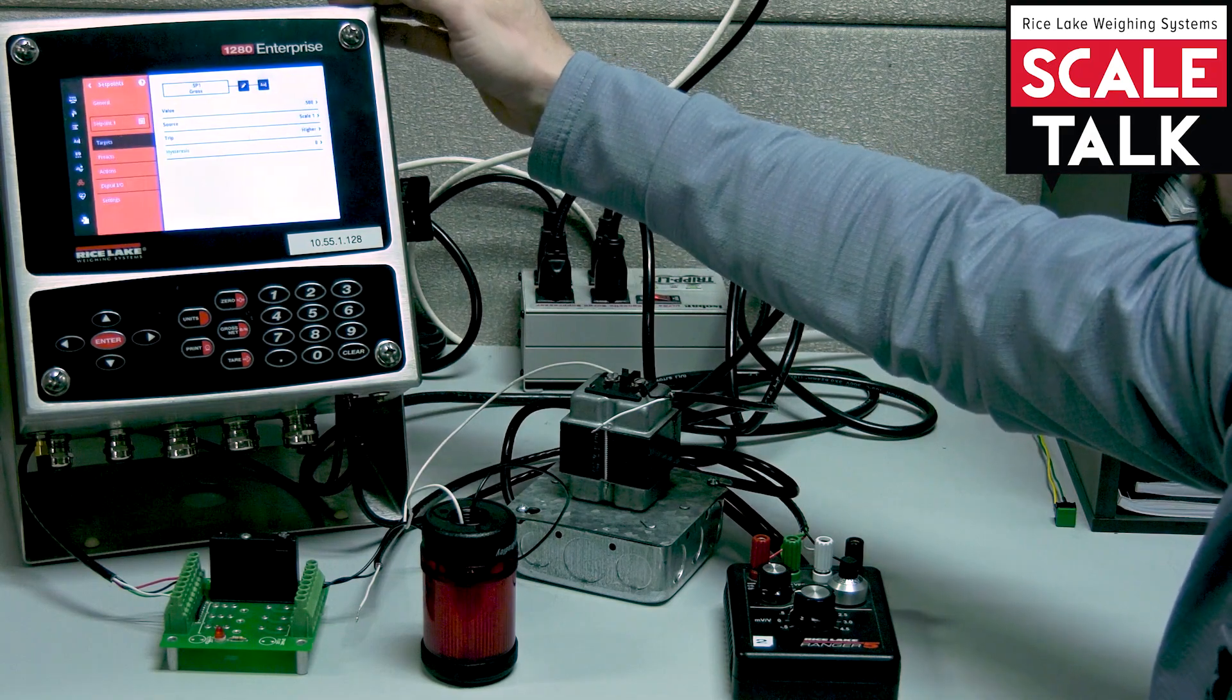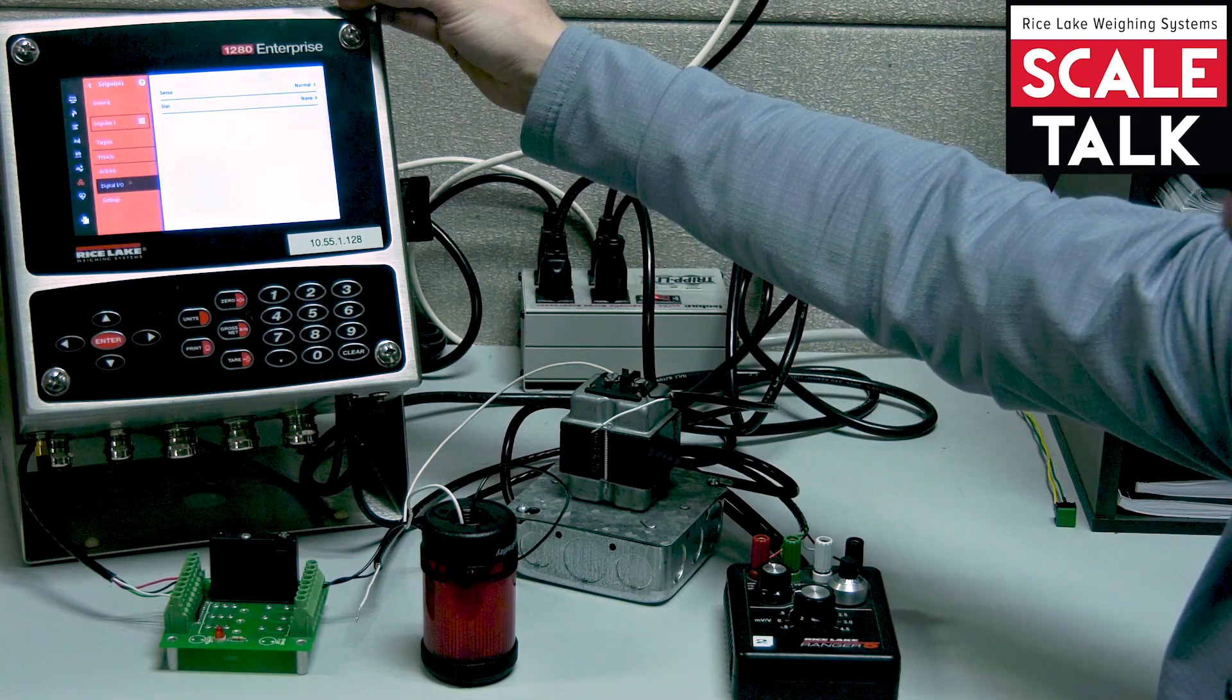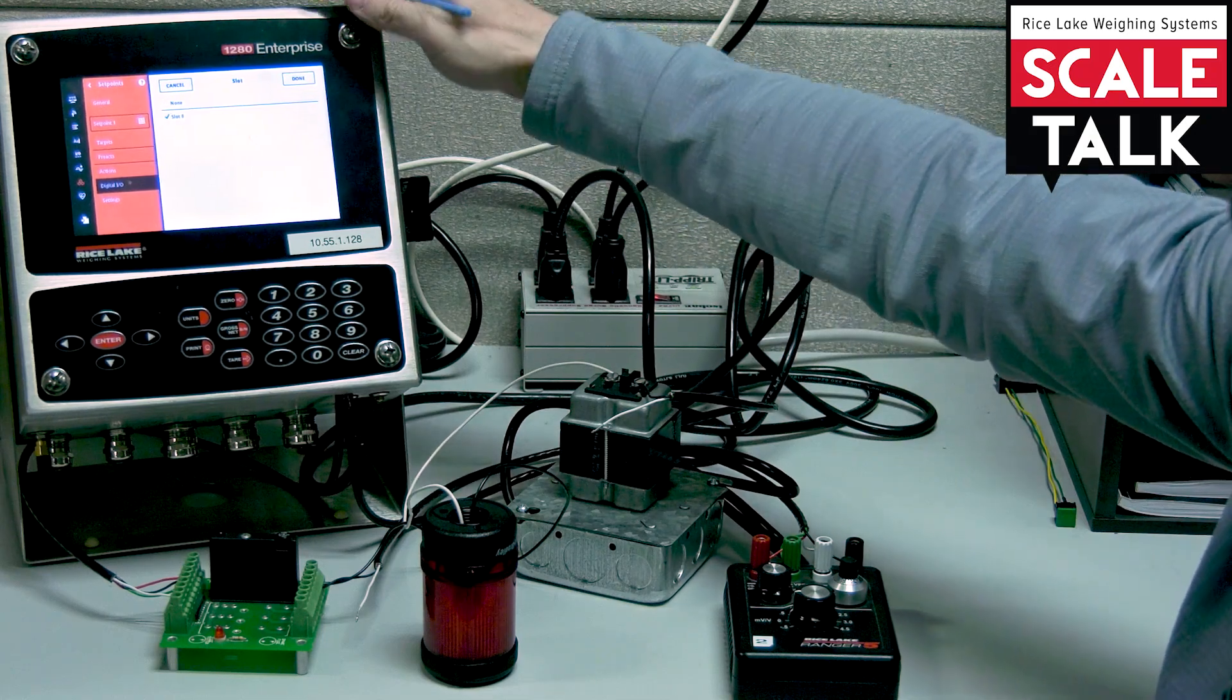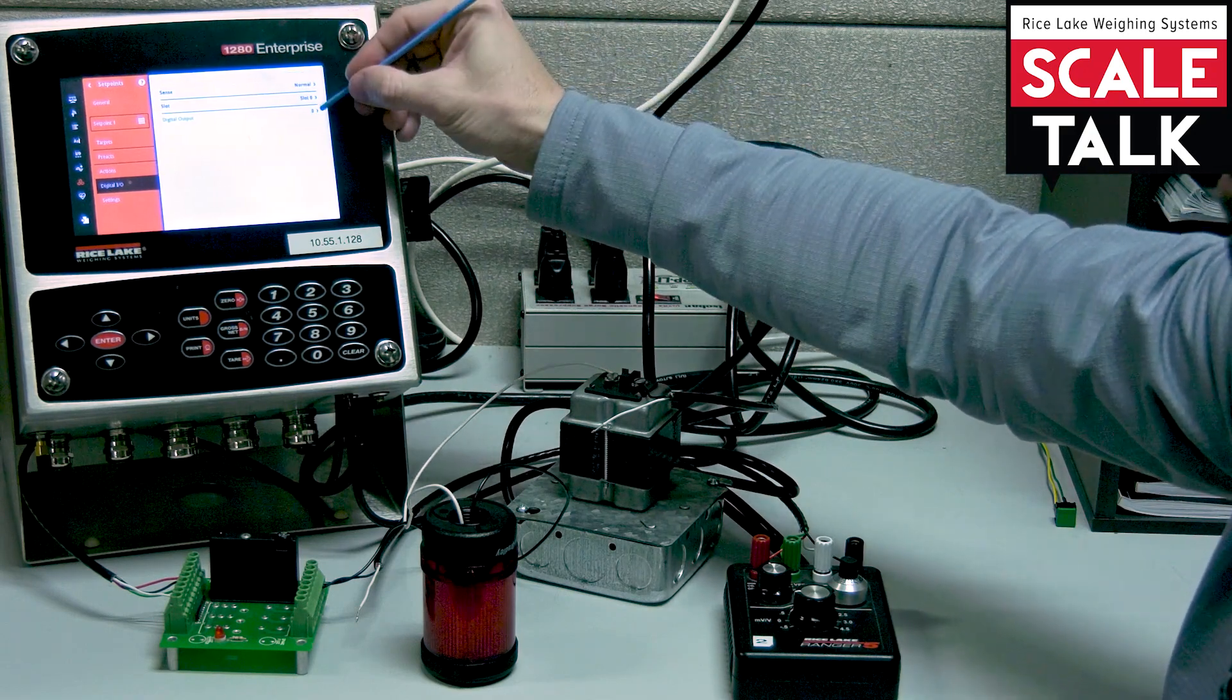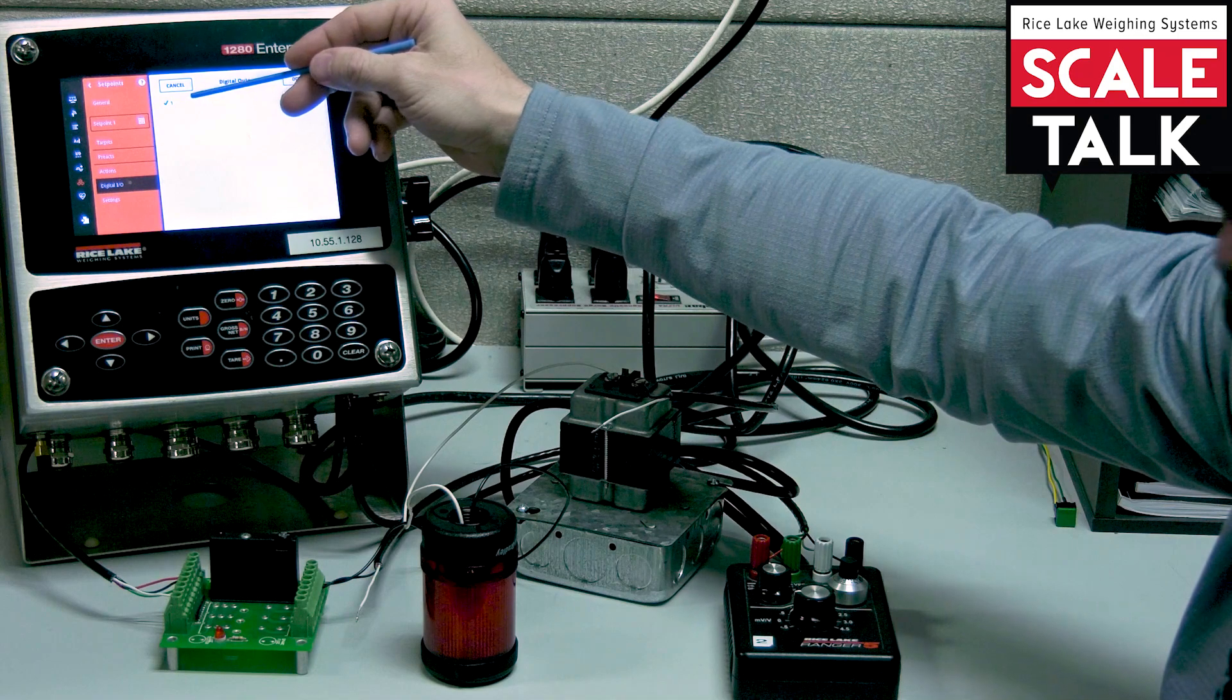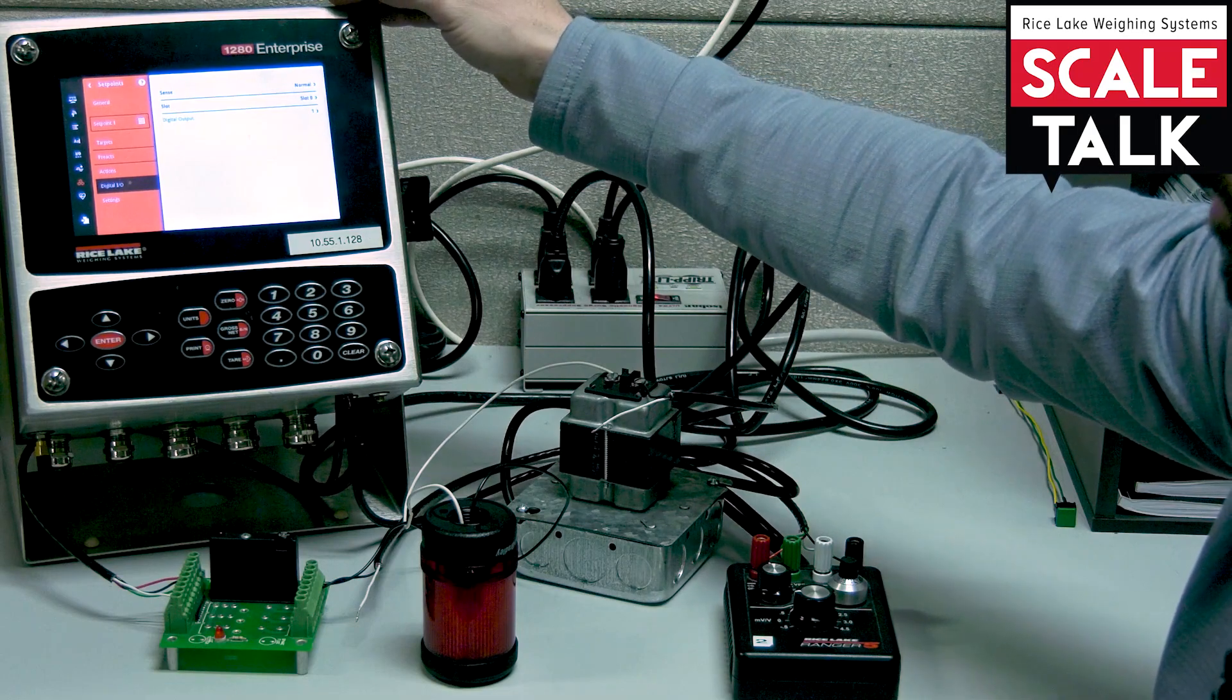Then under my digital I.O., I need to tell it which digital I.O. is going to be affected once we reach that set point. So I'm going to choose my slot zero, which is the native I.O.s to the CPU board. That's where I have that wired up. I'm going to select output number one. You see that that's available now. None of the others are available. Only ones we're going to see are the ones we've pre-configured. So again that's why we had to indicate that first.